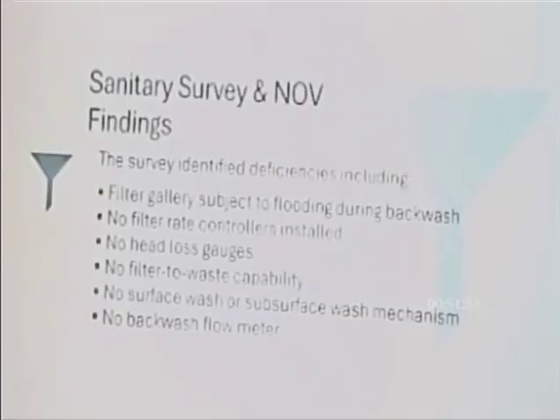We don't have flow meters down there on the existing piping. That's something that wasn't required when these were there. The loss of head gauges, there are actually some old Venturi meters down there that were used for that could measure flow rate and loss of head across there, but they're not in a condition where we could accurately read the pressure and flow across those meters anymore. Those aren't used anymore. Typically now you see insertion meters or magnetic flow meters rather than the old pressure differential devices that we utilize to measure flow rate.